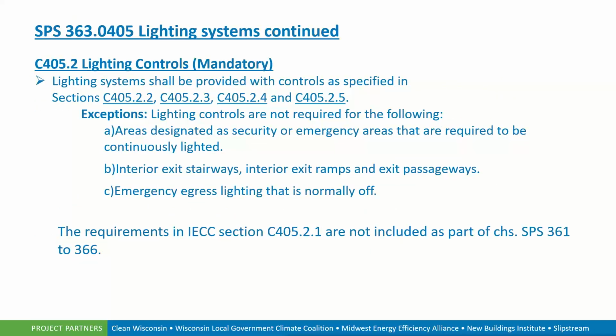Lighting controls shall be provided, or the lighting system shall be provided with controls as specified in C405.2.2, .3, .4, and .5. And that gets deeper into how the lighting control is required for certain areas, along with the daylighting requirements and so forth. Now, these lighting controls are not required for areas designated as security or emergency areas. They are required to be continuously lighted. We don't want to be able to shut the lighting off in those areas. Interior exit stairways, interior exit ramps, and exit passages need to be fully lit at all times, and emergency egress lighting that is normally off is not required to be on these switches. This also tells us that Section 405.2.1 is not included in the SPS 361 to 366. Again, another section that is omitted from the code.